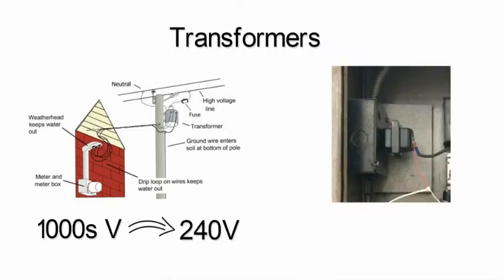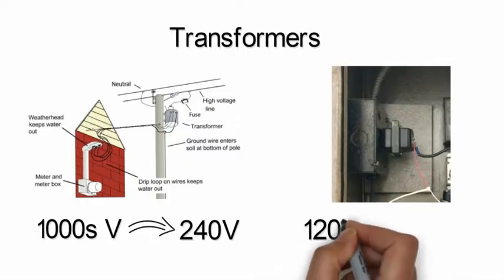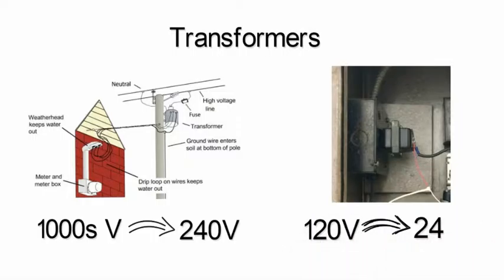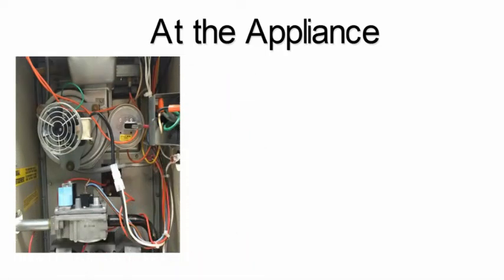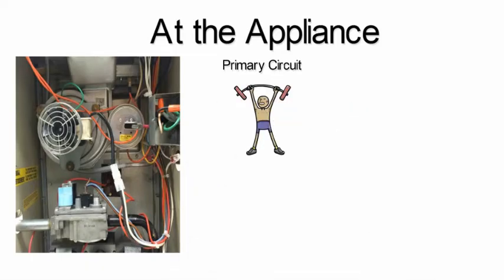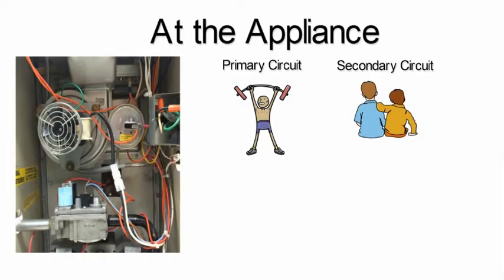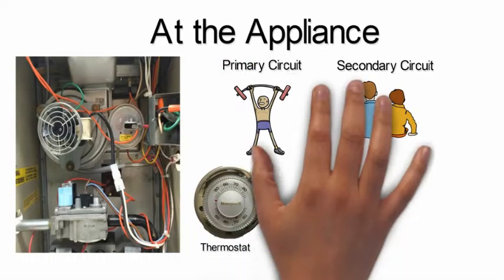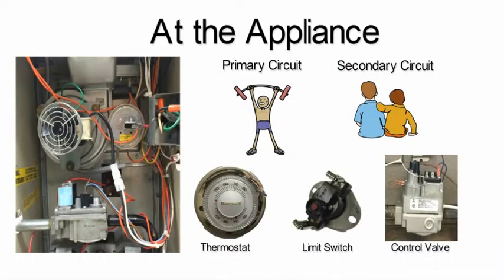Inside gas appliances, transformers are a lot smaller. Step-down transformers reduce the higher voltage primary input from 120 volts into 24 volts on the secondary lower voltage side of the transformer. At the appliance. Inside an appliance, there are two kinds of circuits. The primary circuit, which supplies a higher voltage to the components that require it, and a secondary circuit, which provides a lower voltage to the necessary components. In many cases, the only low-voltage components you need to be aware of are the thermostat, limit switches, and the control valve.